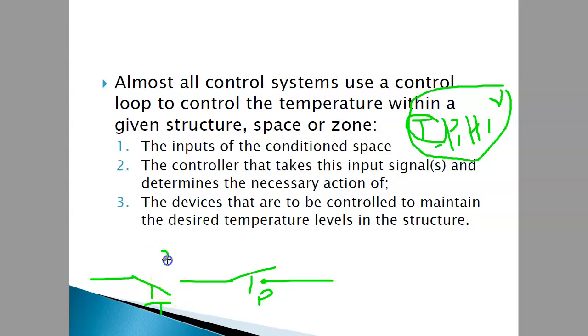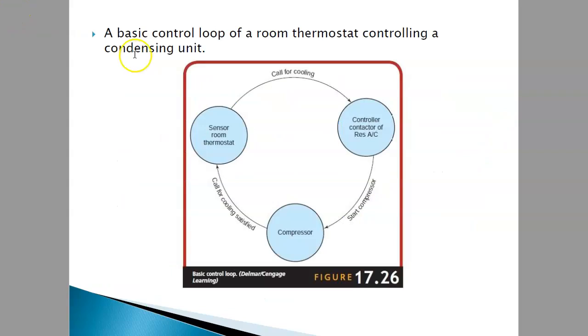For example, if it reaches 26 degrees Celsius, then what happens? The system will be operated, and so on. Same goes for the humidity and also for the flow. If there is no airflow inside the system, the compressor will not run. So it depends on the programming.